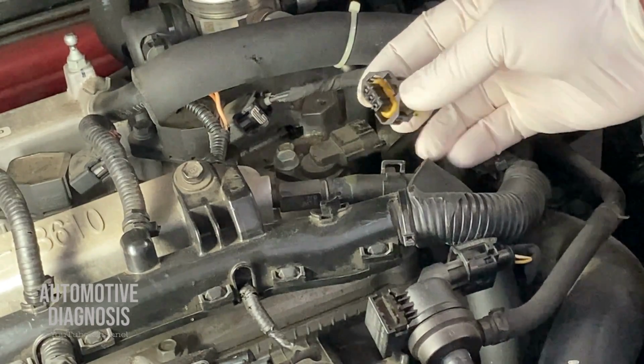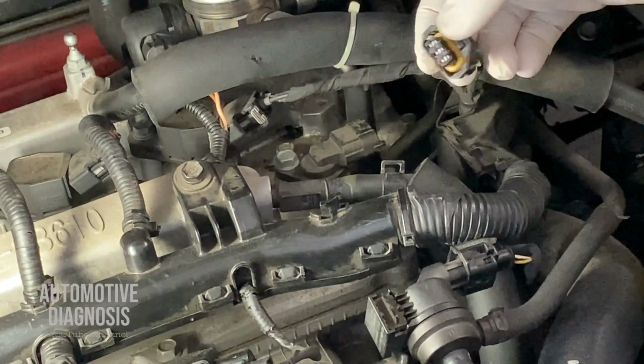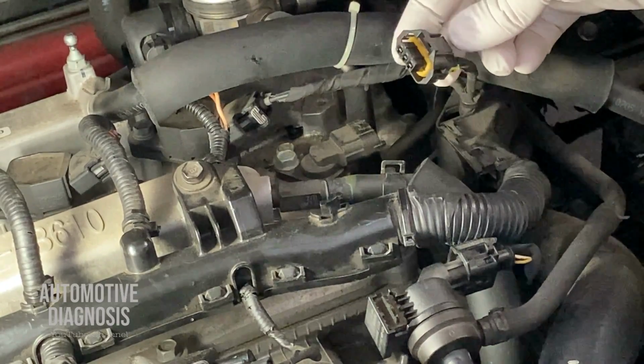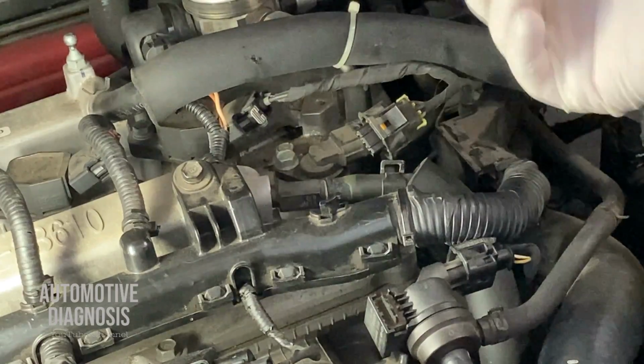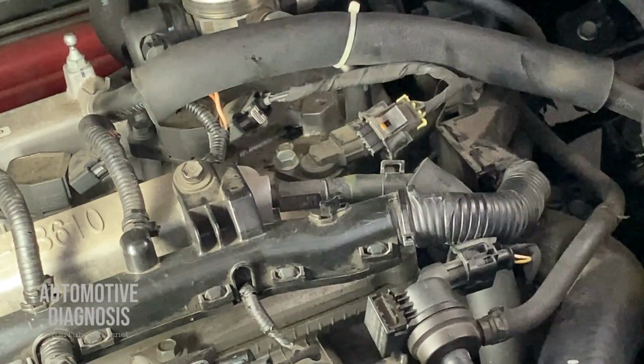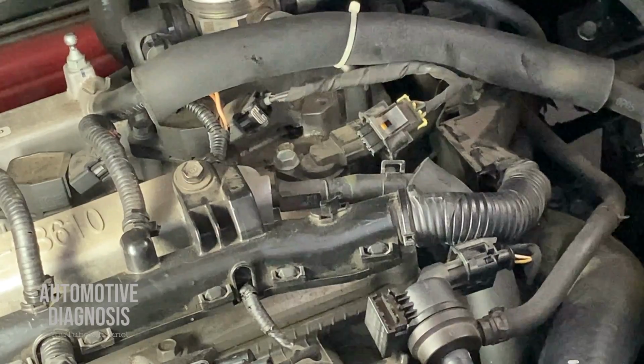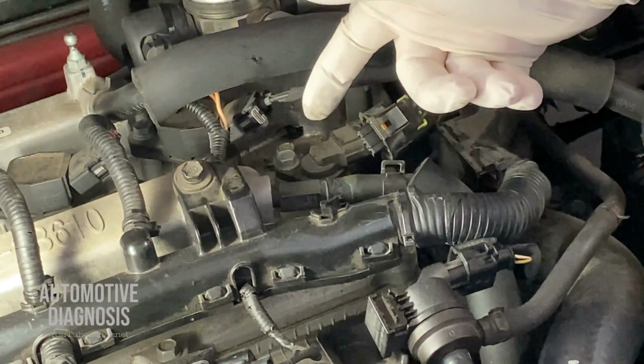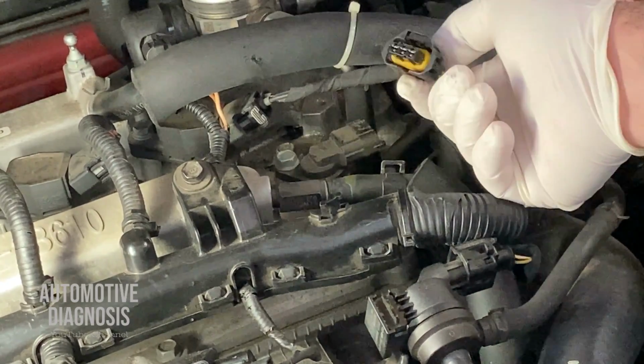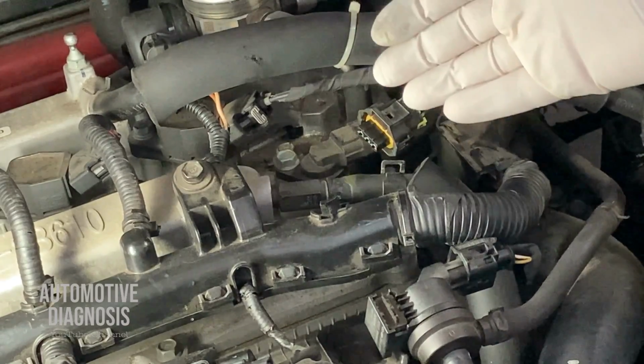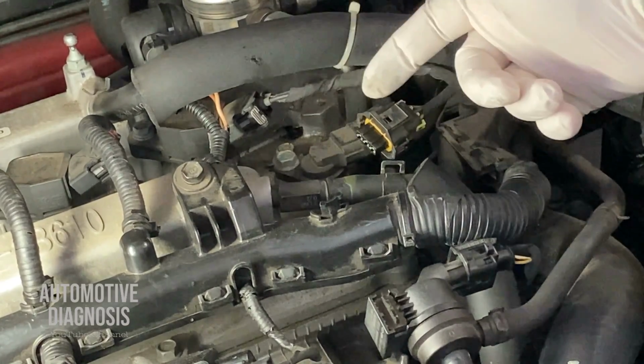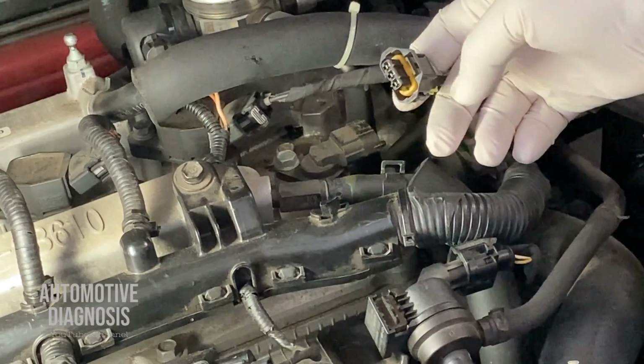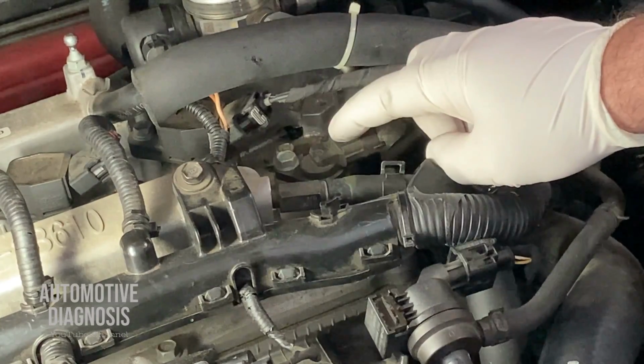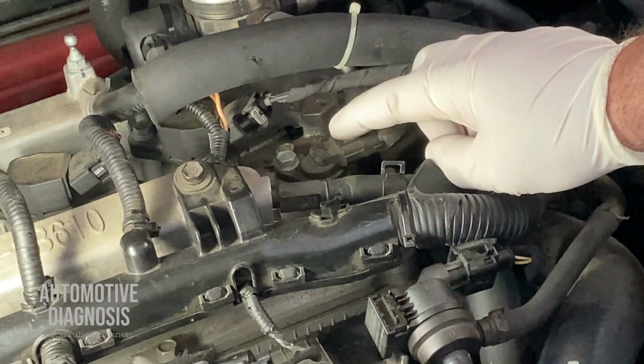We also need to inspect the wiring. There are 3 wires, and the wiring could be the cause of this problem too. The ECM can cause this fault as well, but that's generally not very common. So we focus on the sensor itself and the wiring, going step by step to find the main cause.